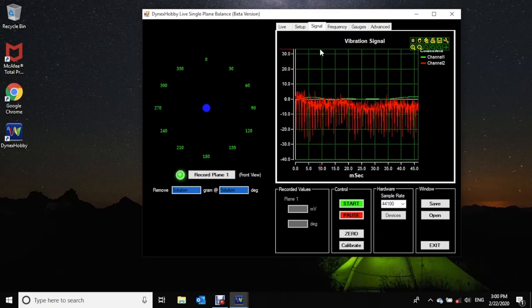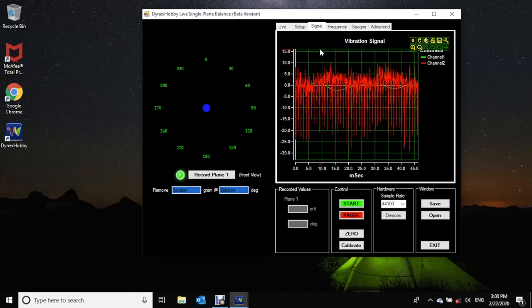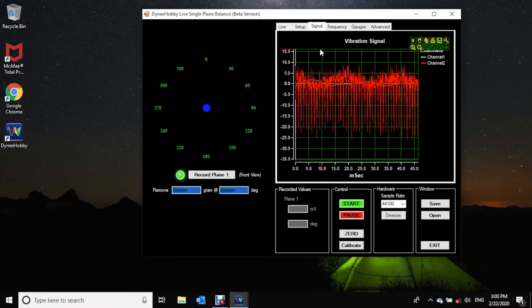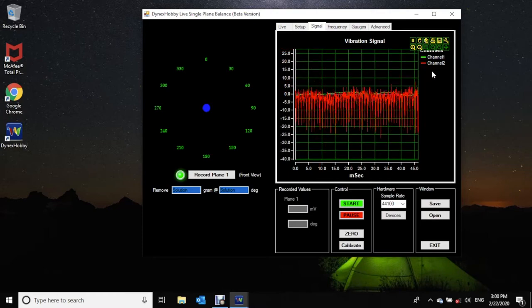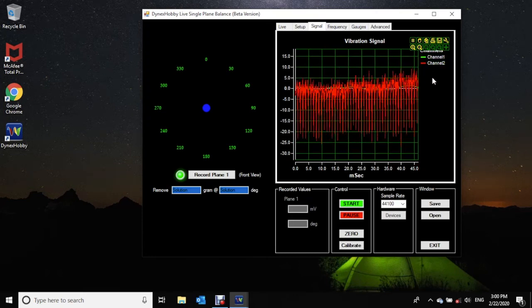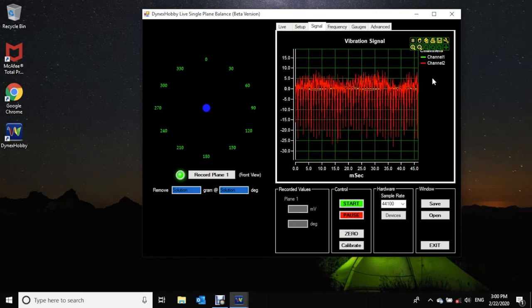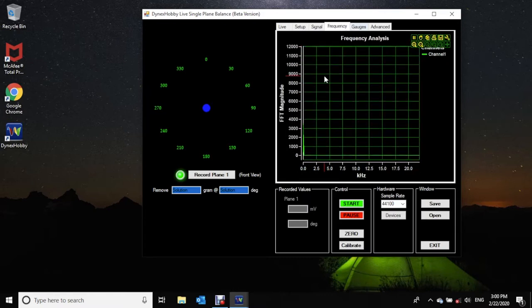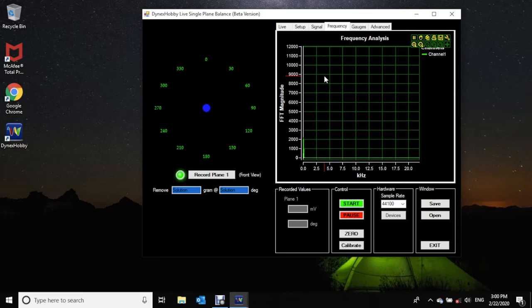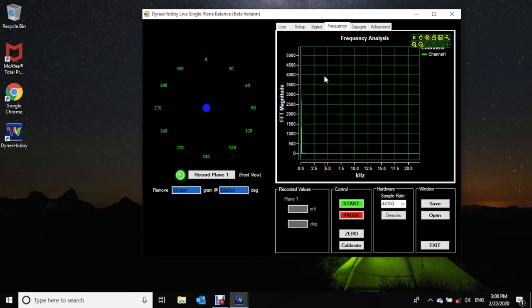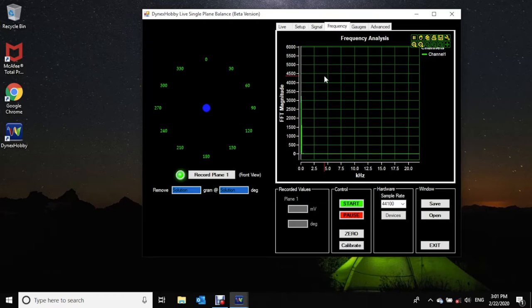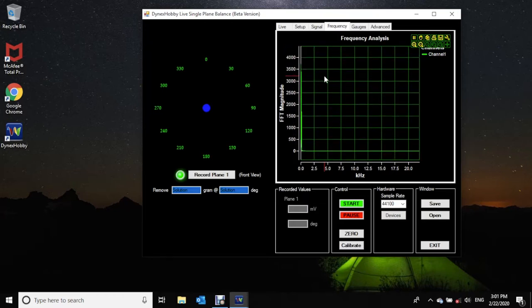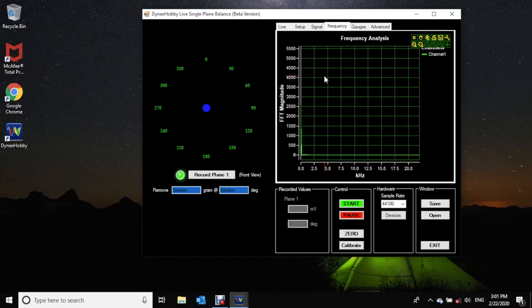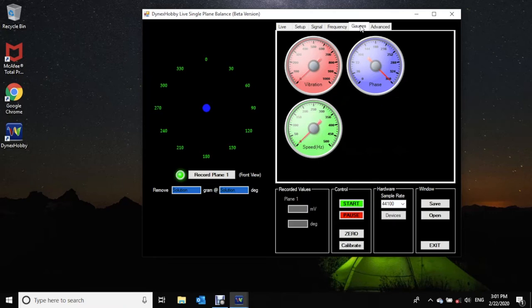There is another plane which demonstrates the signal. There are two signals: one from the infrared sensor and the other from the actual vibration sensor, or the accelerometer itself. Generally, what I tend to do is turn channel 2 off, because its signal is so much larger than the vibration. There is another plane for measuring frequency. It shows you the main imbalance frequency, and if there are other frequencies which also appear in the spectrum, that could indicate there might be other issues associated with the EDF. There are also some gauges where you can see the phase, vibration and the speed of the EDF.